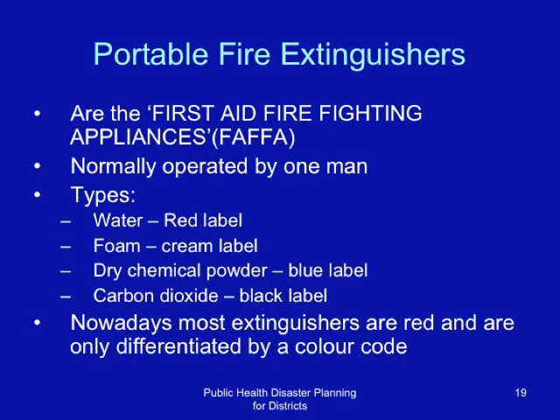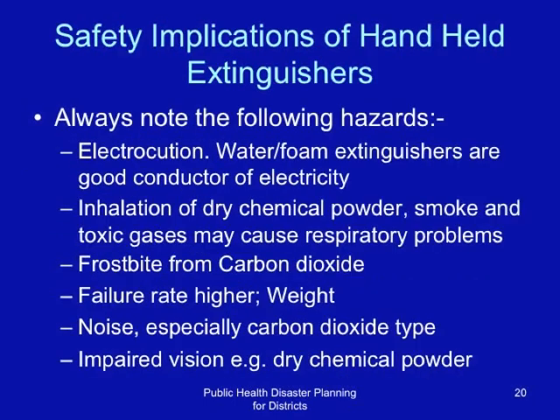Safety implications of handheld extinguishers: always note the following hazards when using extinguishers — the possibility of electrocution, inhalation of dry chemical powder, frostbite from carbon dioxide, higher failure rates, the issue of weight, and noise, especially from carbon dioxide extinguishers. Dry chemical powder extinguishers may cause impaired vision when used.